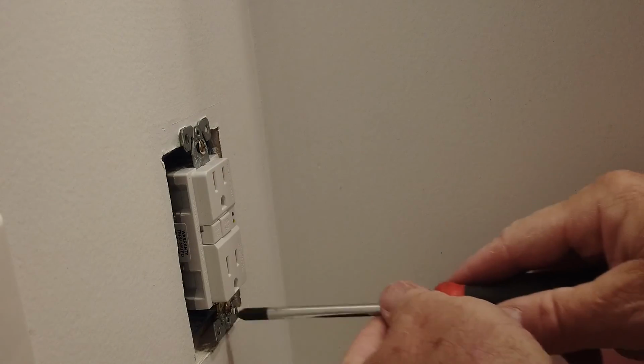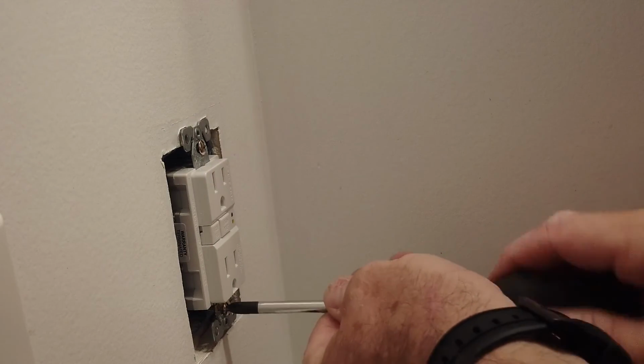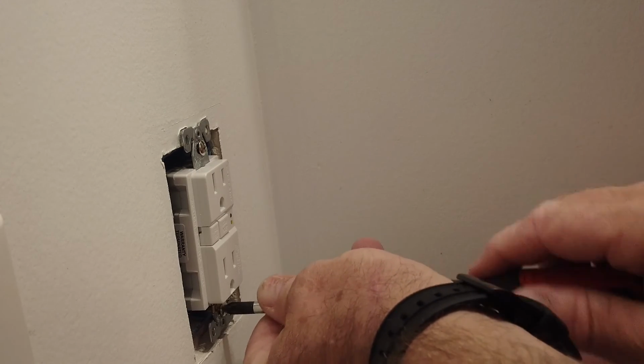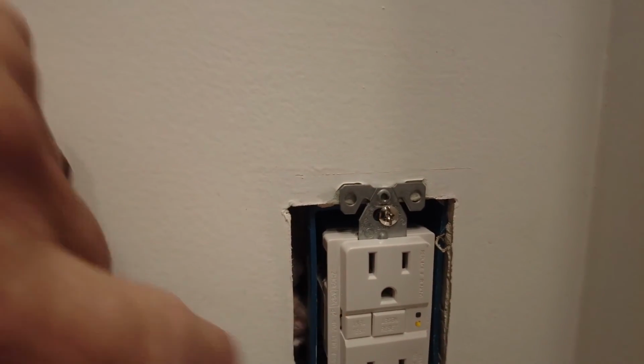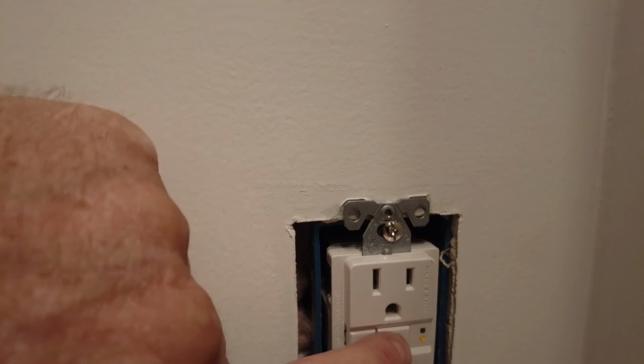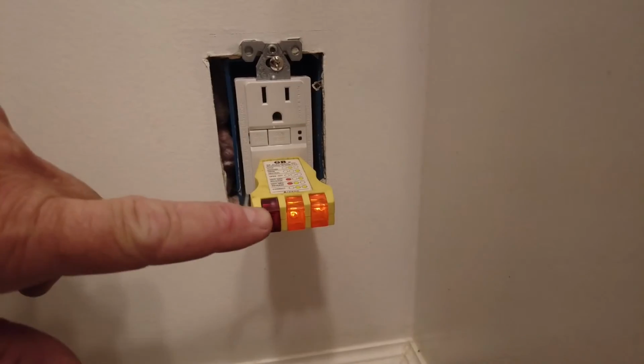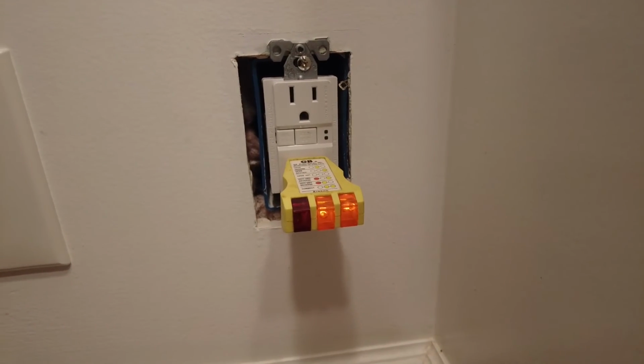That's tight, and the bottom's tight. So I've got the outlet screwed into the wall. Let's give it a test. Test—it tripped it. Reset. No red, two yellows, means it's correctly wired.